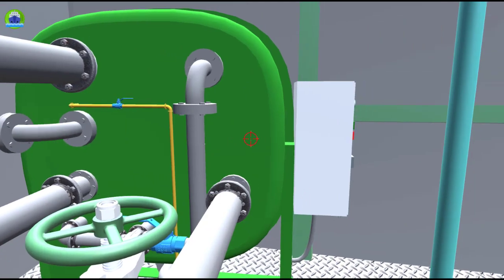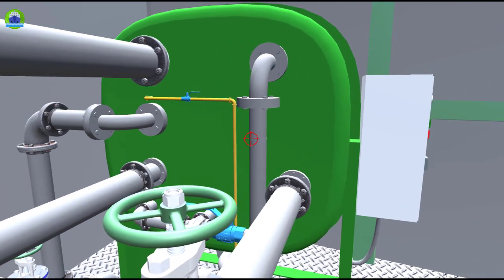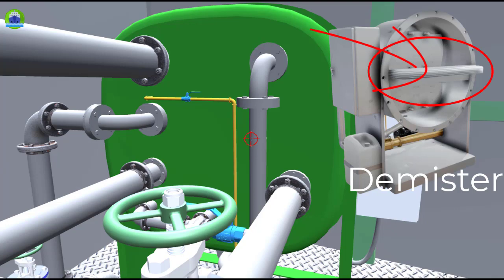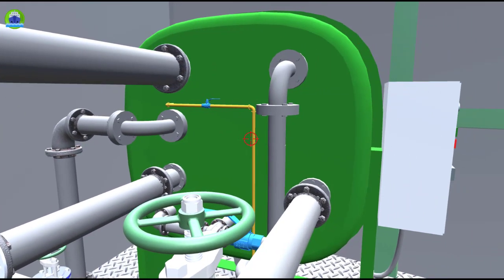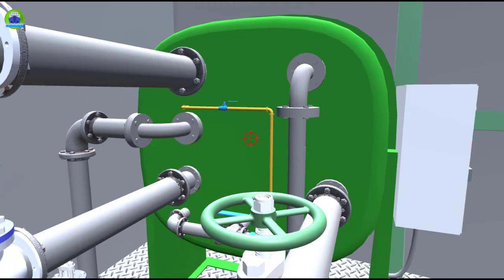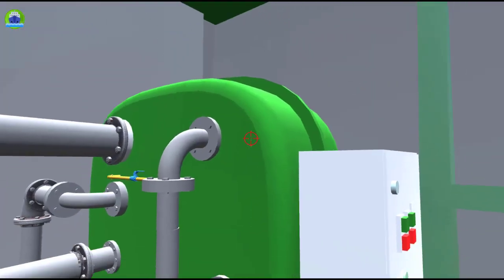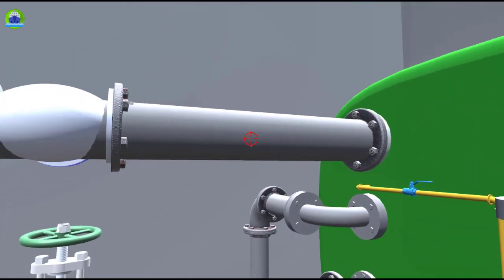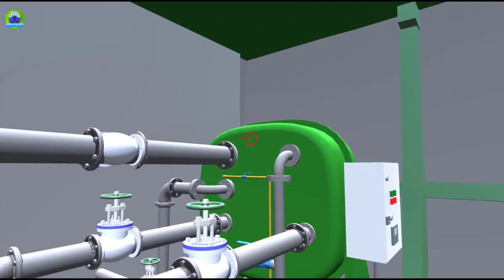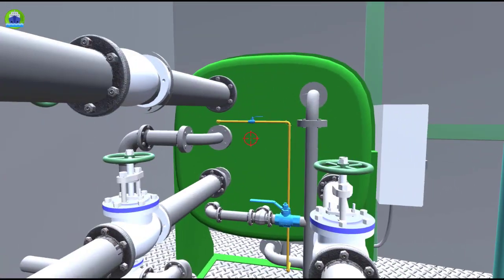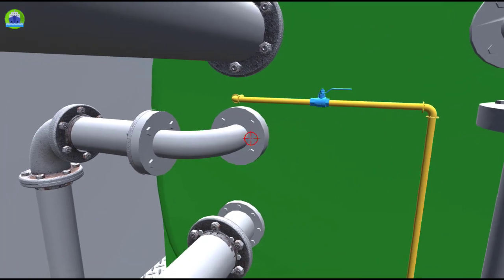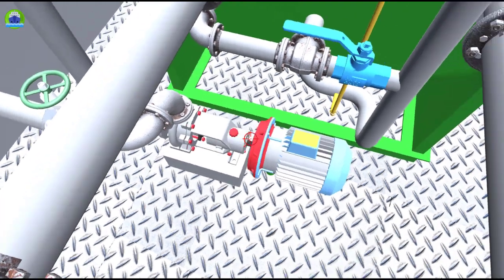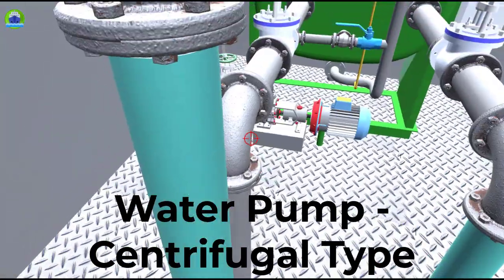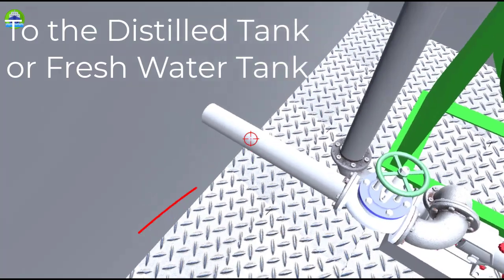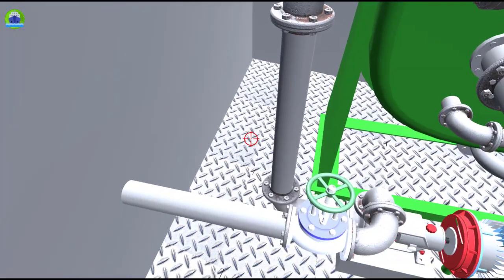It passes through inside, in between the shell, wherein we call it a demister. That demister will further filter the vapor or mist, taking out the salt water that can be carried within. And with that, it goes as a mist through the upper chamber, and we have the condenser, which is cooler in temperature, thereby the vapor or mist will be condensed. Hence, after that, it turns into liquid and it will be sucked out or drawn by the water pump. And from the water pump, it discharges and then goes to your so-called distilled tanks, wherein I'll be showing you.